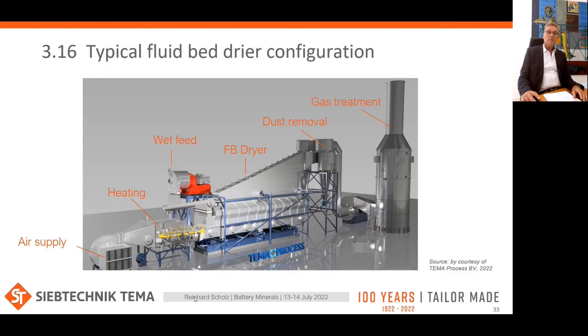This slide shows a typical configuration of a fluid bed dryer. A screw conveyor is used, usually installed between the centrifuge and the inlet of the dryer, leading upwards to prevent centrifuge wash from entering the dryer. Air intake is here on the left side of the slide. Part of the air is heated for drying purposes, in this case by direct gas-fired air heating. The air enters the drying chamber from below. The remainder of the air, not heated, is used for cooling in the second part of the dryer.